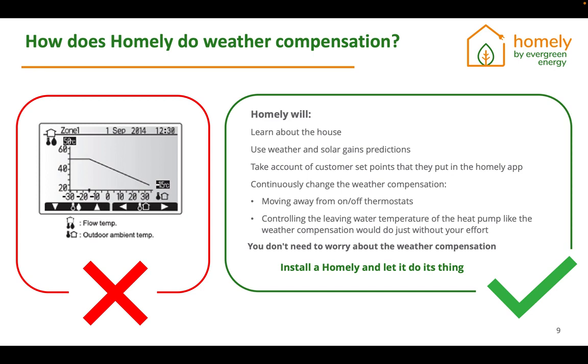Then once we've learned about the house and we know how it behaves in certain weather conditions and at different outside temperatures, we can use the predictions of the weather and solar gains to come up with an optimal heating schedule for this house. And when I say heating schedule, I don't mean an on and off schedule. I mean the flow temperatures that we should be sending to the unit to optimize the heat pump and deliver best in class efficiencies. To do this, we also take into account the customer set points. So as the customer changes their set points, we would amend the flow temperatures that we're sending to the unit.